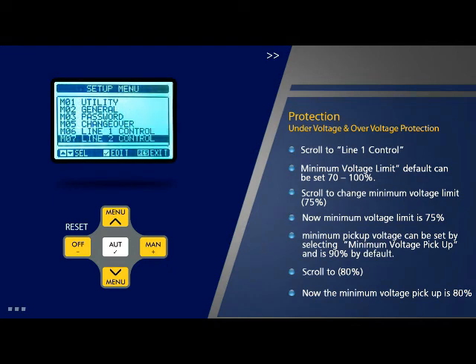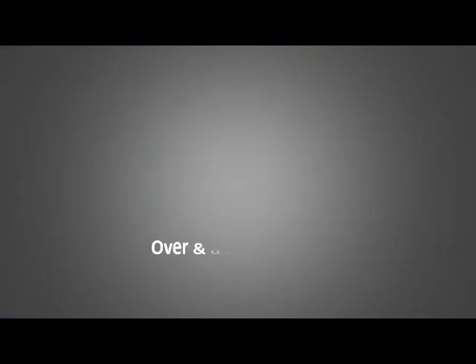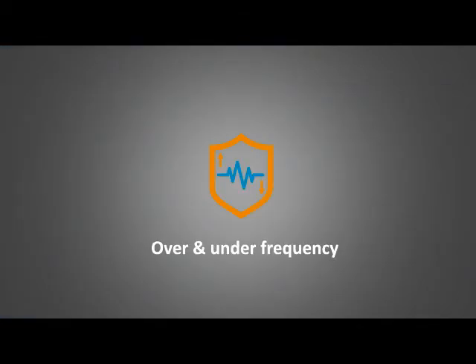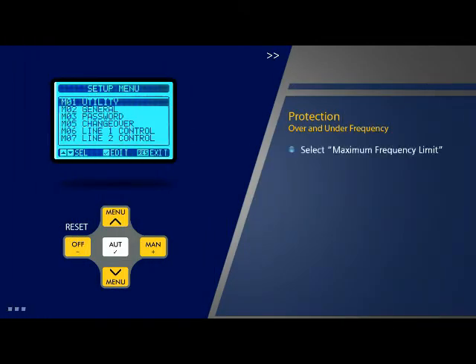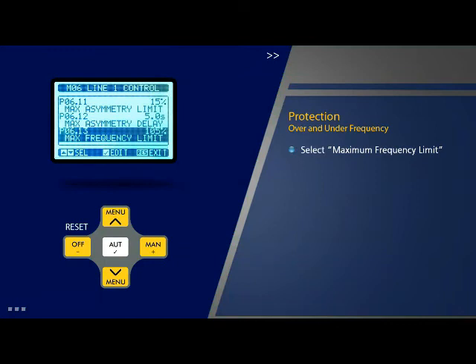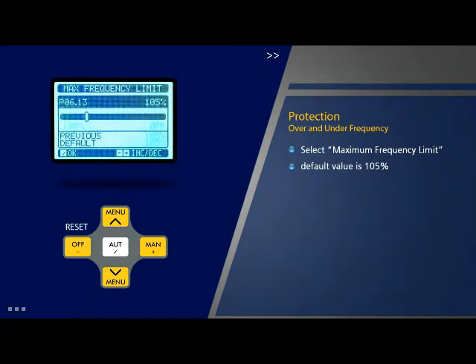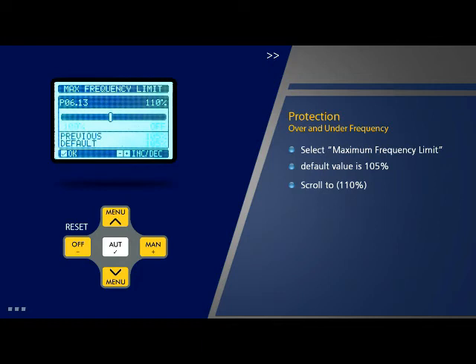Similarly, these values can be set for line 2 by selecting the respective options on the page 'Line 2 Control'. Over and under frequency parameters for line 1 and line 2 can be set as follows: select parameter 13 'Maximum Frequency Limit' on the line 1 control page and press OK. The default value is 105% and can be changed in the range of 100% to 120%. Scroll to change this value, for example to 110%, and press OK. The maximum frequency limit is now changed to 110%.